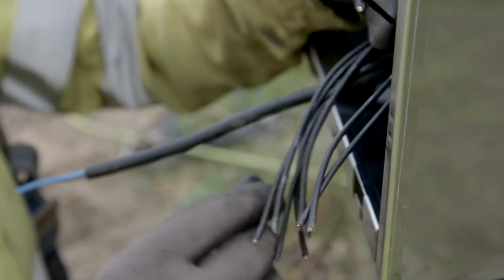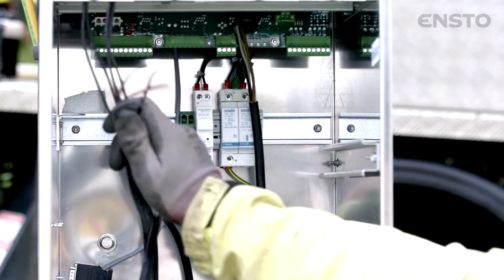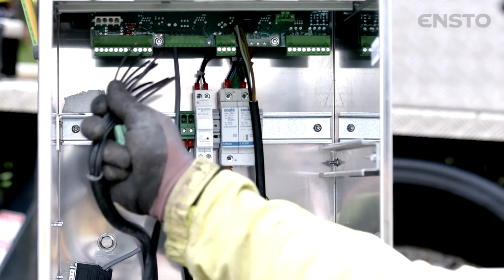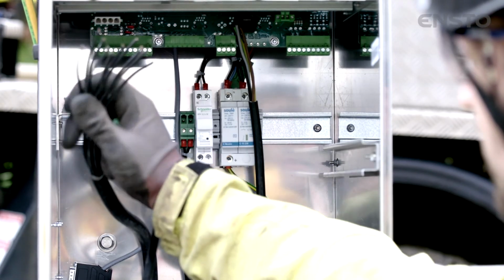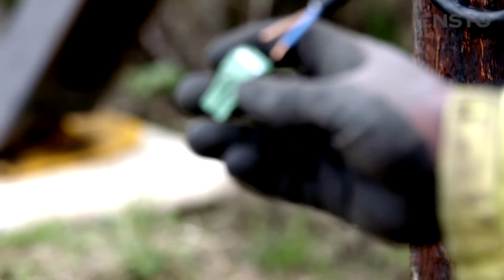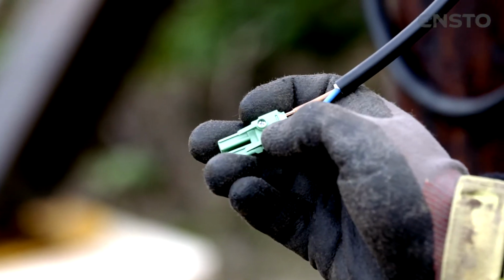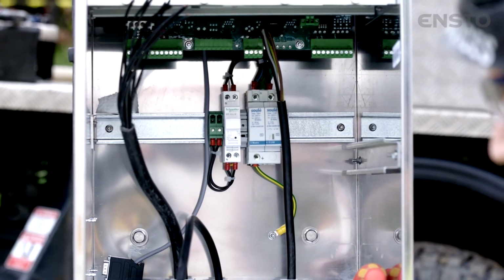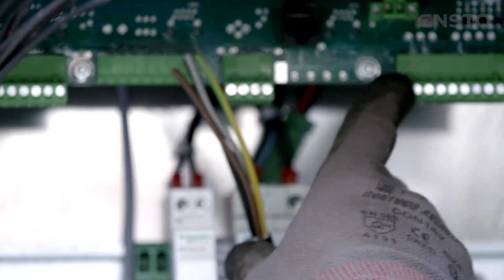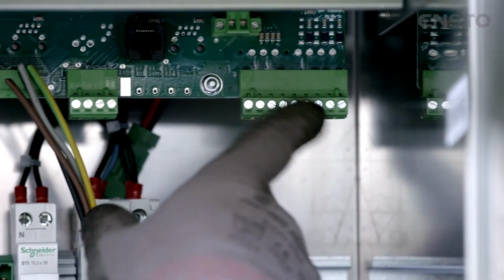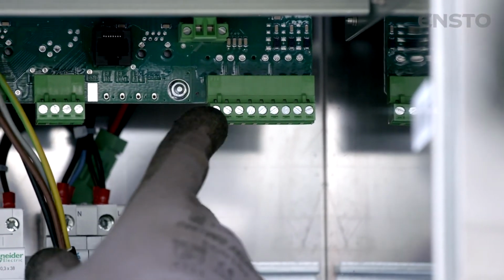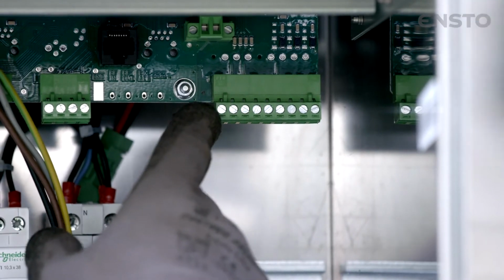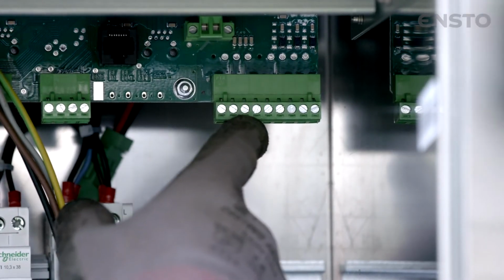A 10-core control cable terminates into the motherboard on the far left side. The cores are numbered 1 to 10 and should be connected left to right. The 2-core power cable should be terminated onto the live and neutral plugs and connected as labelled on the DIN rail. Then terminate the 4-core cable into the 9-terminal block on the right-hand side of the motherboard. Install left to right, brown, black, grey, and earth.